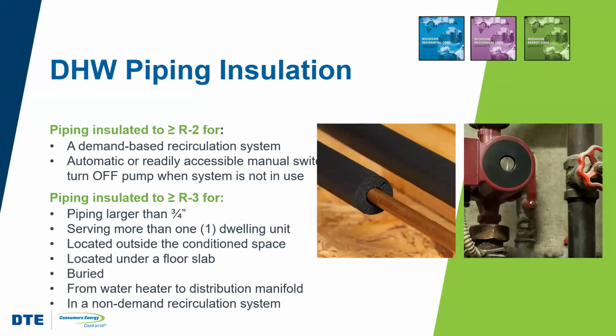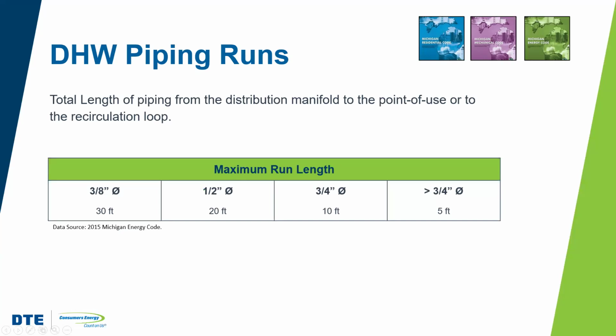We want our domestic water piping to also be insulated, similar to the hydronic system. And the insulation will vary depending on whether or not there is an on-demand or non-demand recirculating system, right? So if there's a recirculating system, but it's non-demand based, then the insulation needs to be R3. If it is demand based, then the insulation can be R2. We want to limit the length of domestic hot water pipe runs, right? This is for faster water delivery and for energy conservation. And the code has some maximum limitations on that based on the diameter of the pipe.